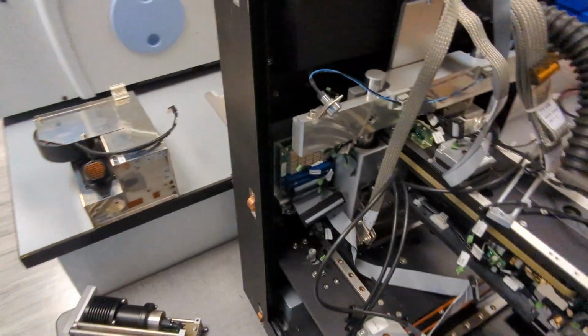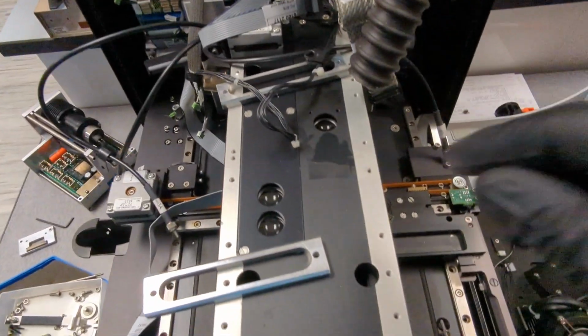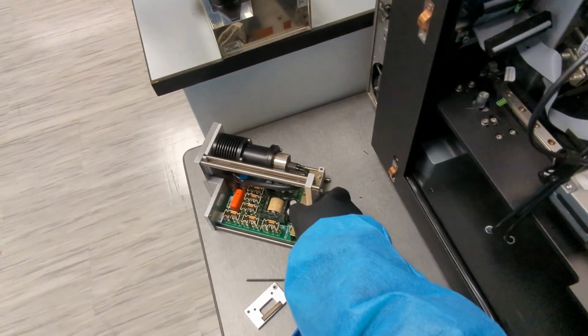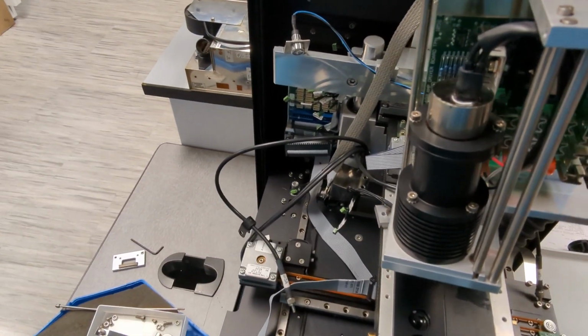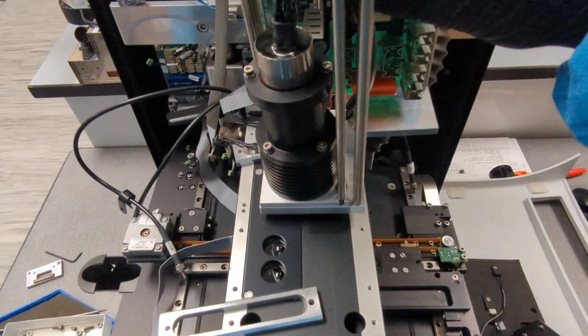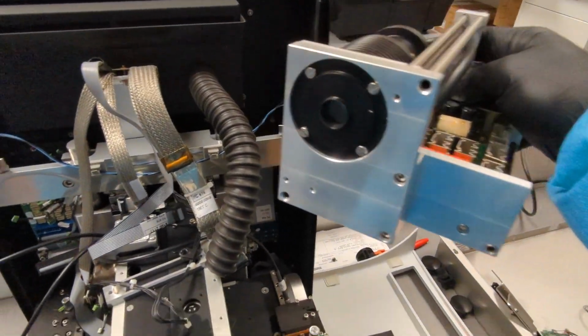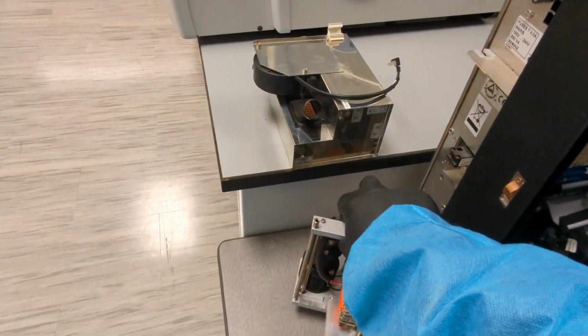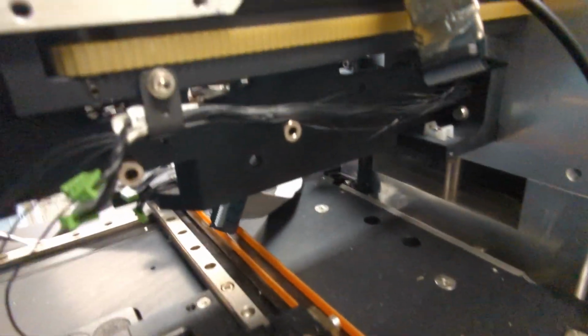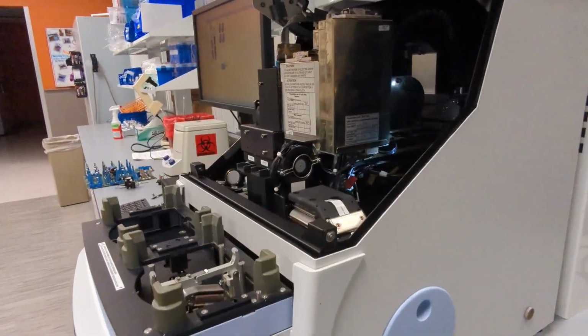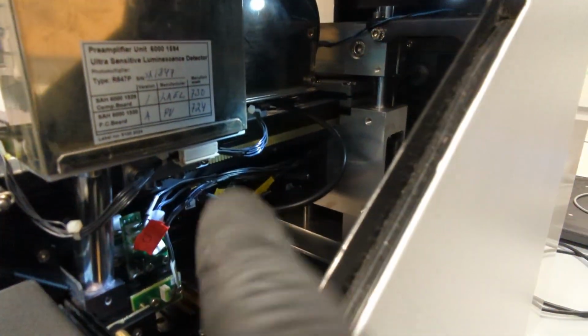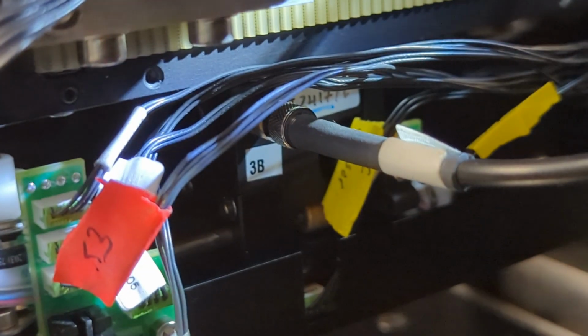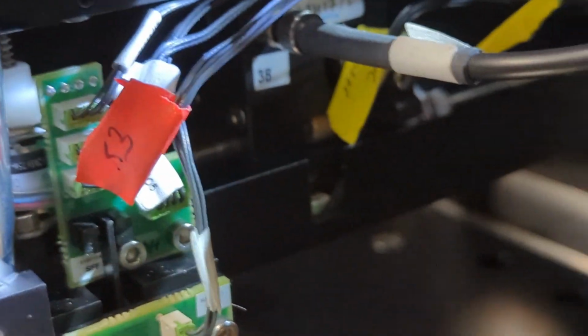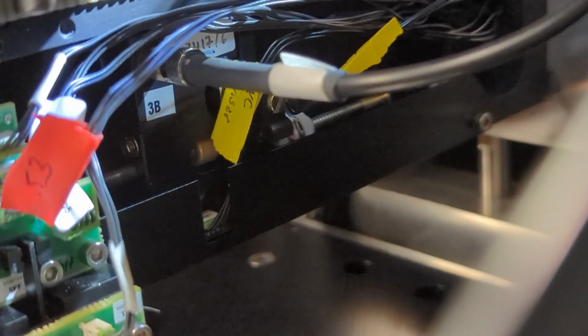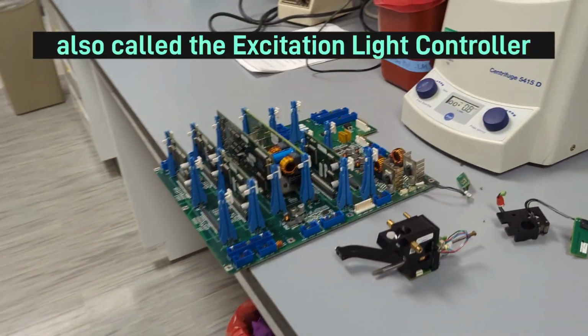Now you can utilize our parts unit a bit more. This lamp is sitting on top of this lens right here, and so if I grab this, it's going to be sitting basically like that. I think it might be oriented a little bit differently, but the point is that it is meeting that lens there. And from there, there's a device that sits right about here after the xenon flash lamp, and you can actually see an optic cable running from it where it says 3B. You can actually see a little stepper motor there with the Acme screw coming out of it. That is the excitation light selector, and I have one of them right here.